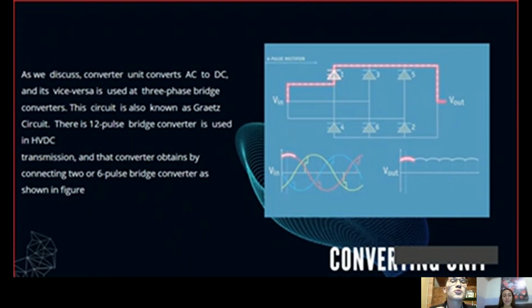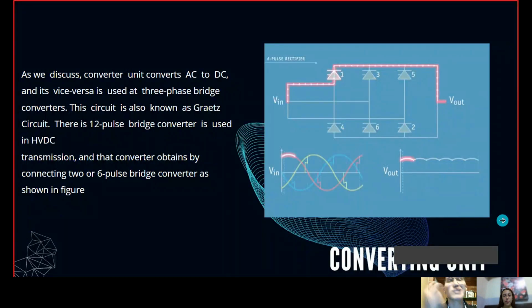Conversion unit. As we have already discussed, the conversion unit converts AC to DC and vice versa. Three-phase bridge converters are used. These circuits are also known as graetz circuits in HVDC transmission, and 12 pulse bridge converters are in use, obtained by connecting two six-pulse bridge converters. As shown in the figure, the semiconductors are activated by pulses in the three-phase bridge, and the sequence of pulses is T1, T2, T3, T4, T5, and T6.